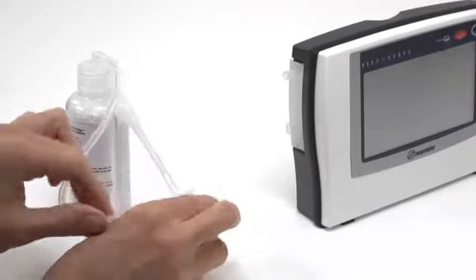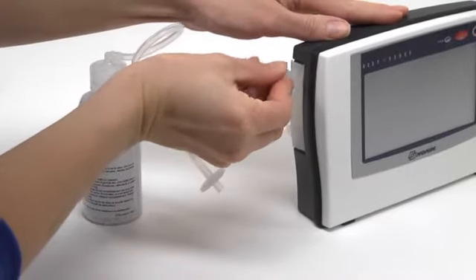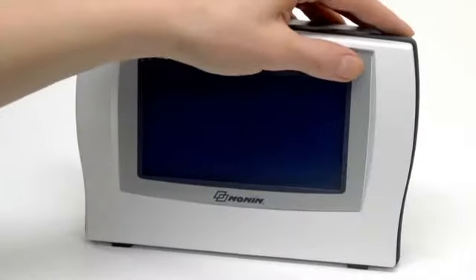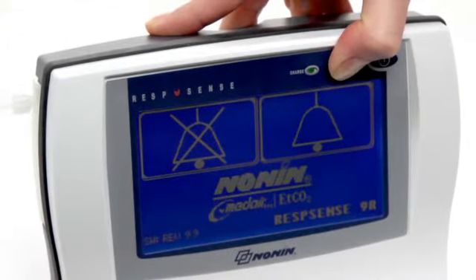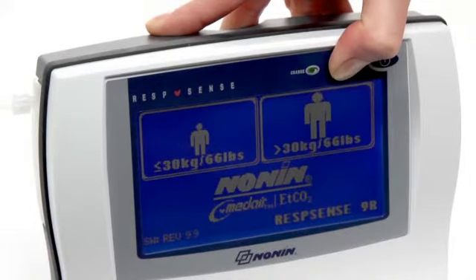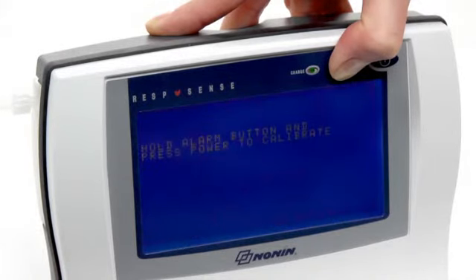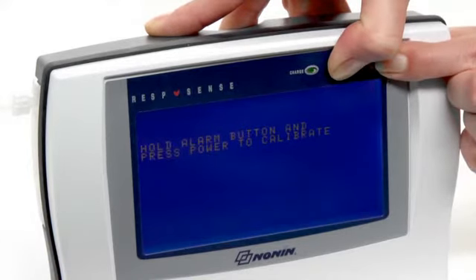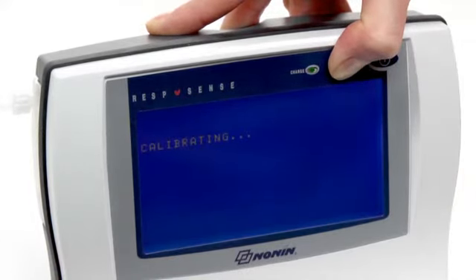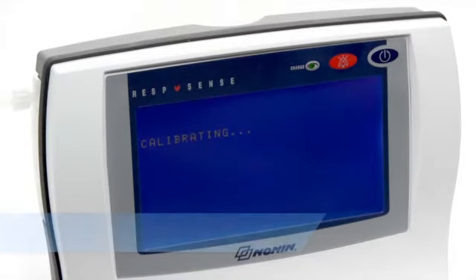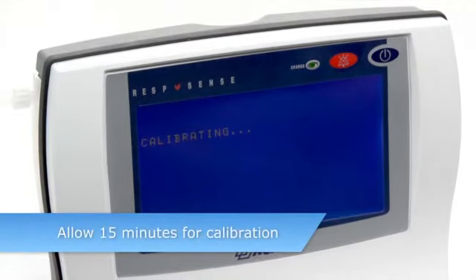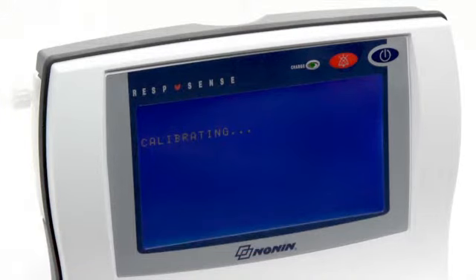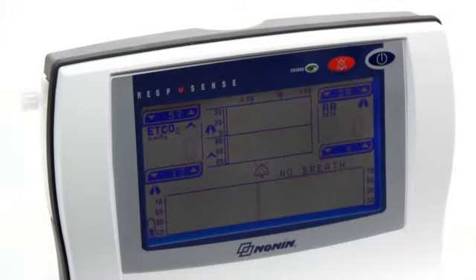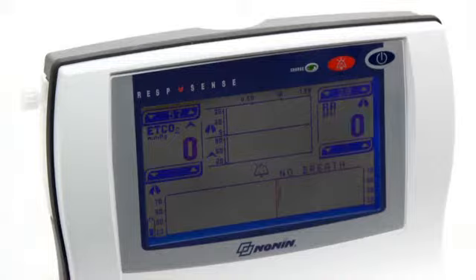First, attach the calibration apparatus to the moisture trap. Turn the monitor on. When the NONIN logo appears, press and hold the audible Alarm Pause/Resume button. Keep that button pressed and press the Power On/Off button at the same time and hold. Calibrating will appear on the display. Then, release both buttons and allow approximately 15 minutes for the monitor to complete the calibration process. The display will return to the normal operating screen when completed. Disconnect the calibration apparatus.